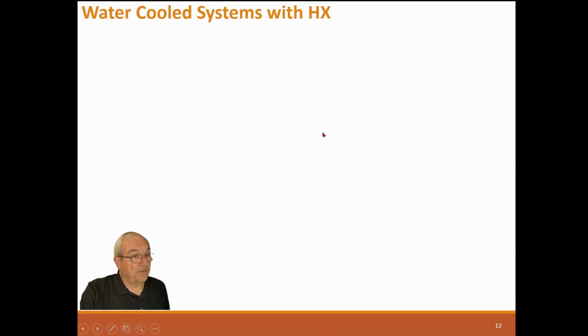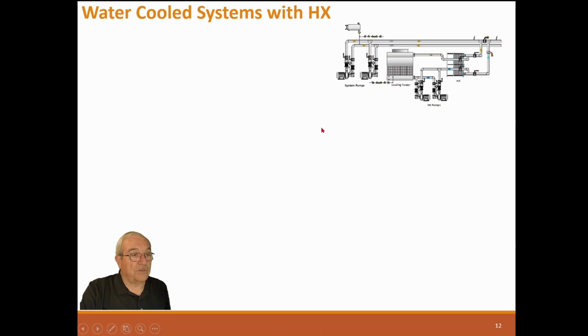So now let's look at a different system. This is a system that we don't see a lot, but the reason this system is popular is because it uses a standard cooling tower, not a fluid cooler. The reason for that is the fluid cooler or cooling tower is the most vulnerable part of the system. The water is very corrosive, and the fluid cooler or cooling tower is the first thing that will degrade and have to be replaced. Well, the fluid cooler, because it has that large steel heat exchanger, is very expensive. It also takes more power to run the air through that heat exchanger. So they're not very energy efficient, and they're really expensive to replace.